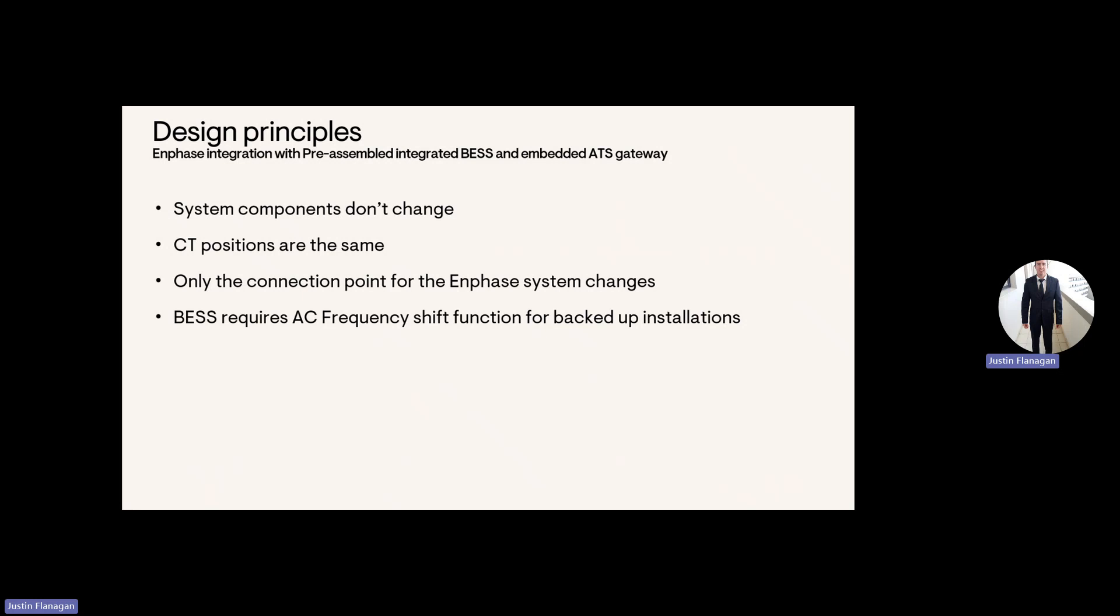And then design principles. So system components don't change with Enphase. The CT positions are the same. Only the connection point for the Enphase system changes. So that will be connected onto the generator input of the SunSync hybrid inverter. And the battery requires frequency shift function to be AC coupled.